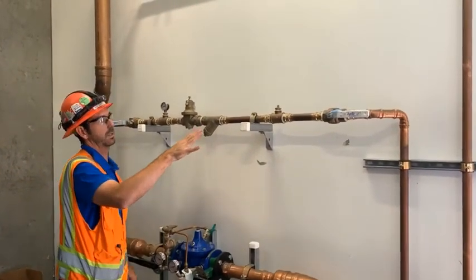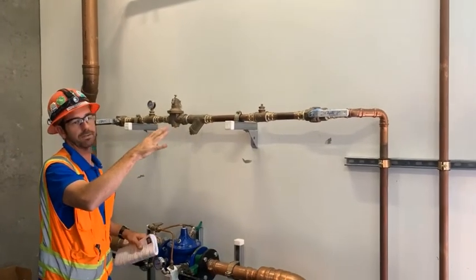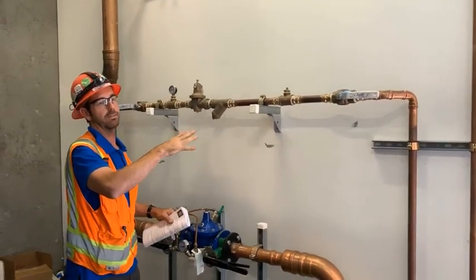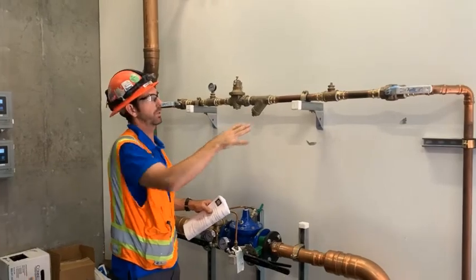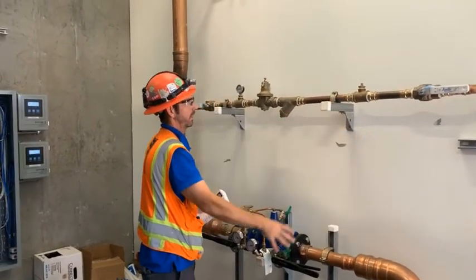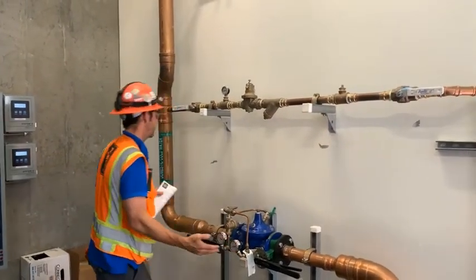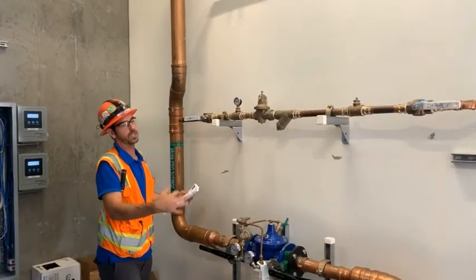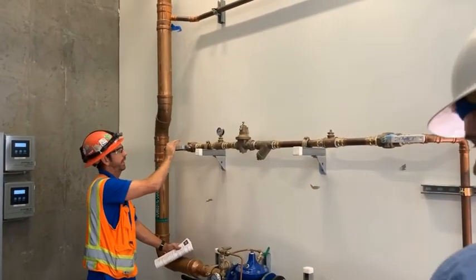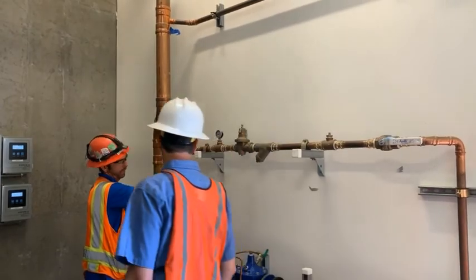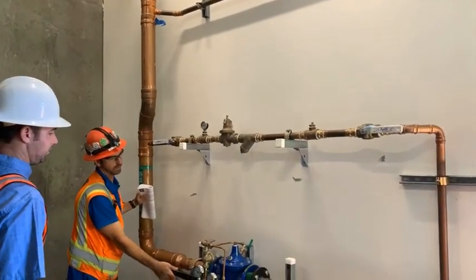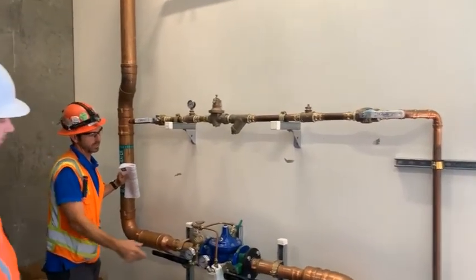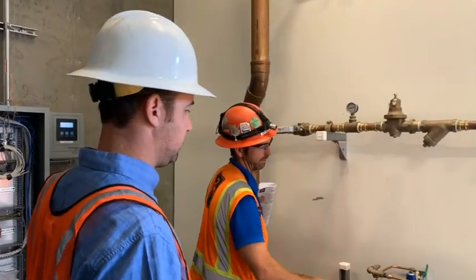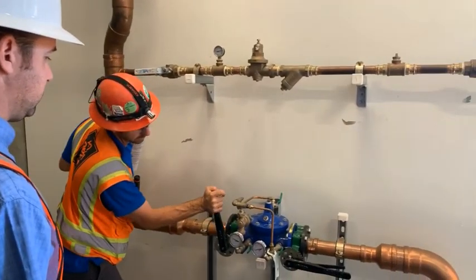Remember, if we do have a catastrophic leak inside of a wall on the domestic system, we're just going to shut the main water off. Let's say that then. So since we're here and you guys prefer shutting the downstream valve of a regulator, we're going to shut this valve right here and this valve right here. That way you have pressure into the valve. Just know when you do that on this style valve, if you close this real quick, it can spike the pressure.